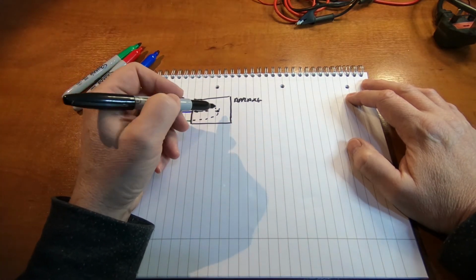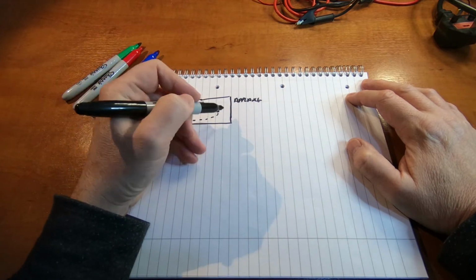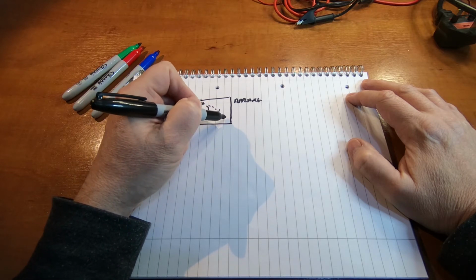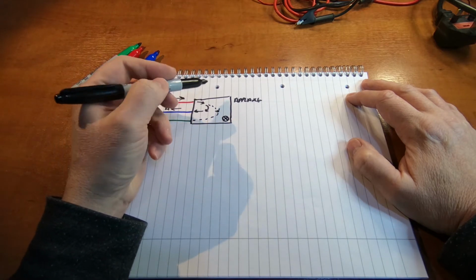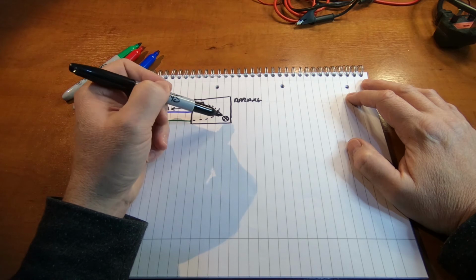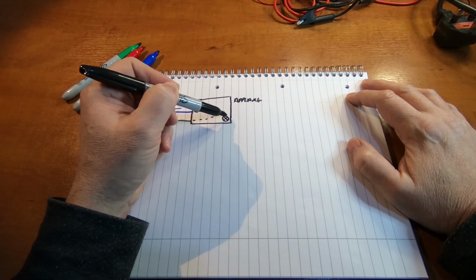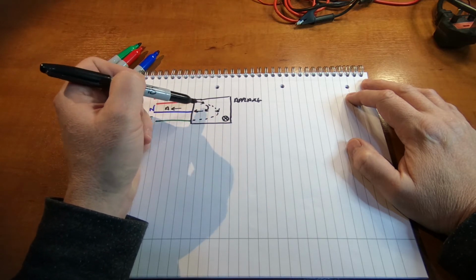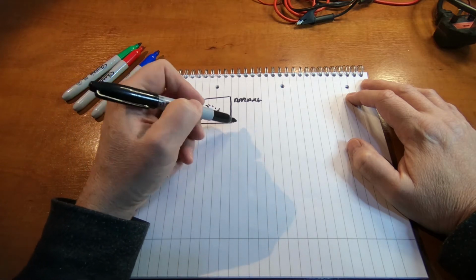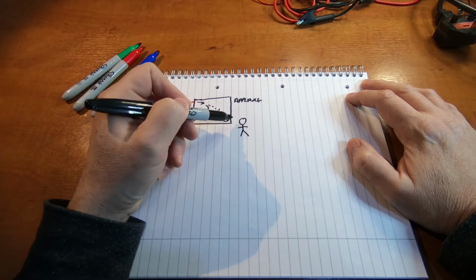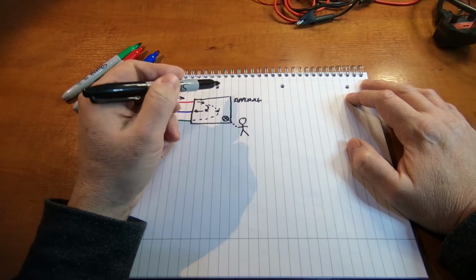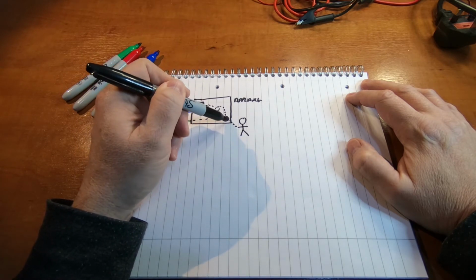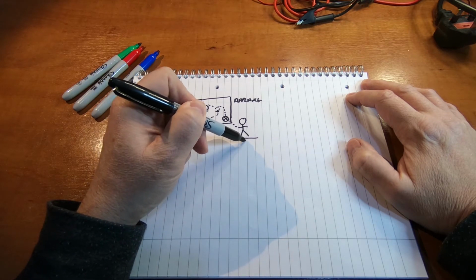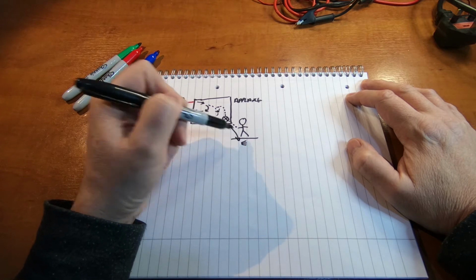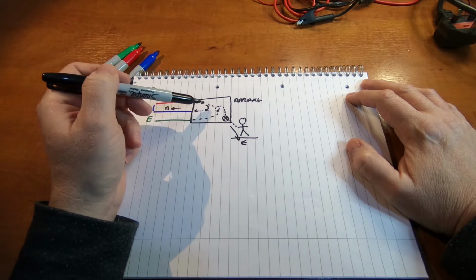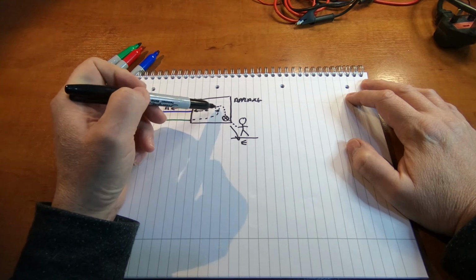Now, another way that you could have earth leakage is through a person touching that appliance. So if you have some metal on the outside of this appliance, let's say a screw, a metal screw, and it's wet inside the appliance, and so there's moisture between the back of this screw or whatever metal is on the outside of the appliance and the live terminals inside. Then if you were to touch that, let's have our guy there, if we were to touch that, then the earth leakage would come through here this way, through the screw, through the person, and to ground basically. So there's earth there, and it would come through this way. So two ways that earth leakage can occur. One is internally in the device through the earth lead, and the other way is through the person.